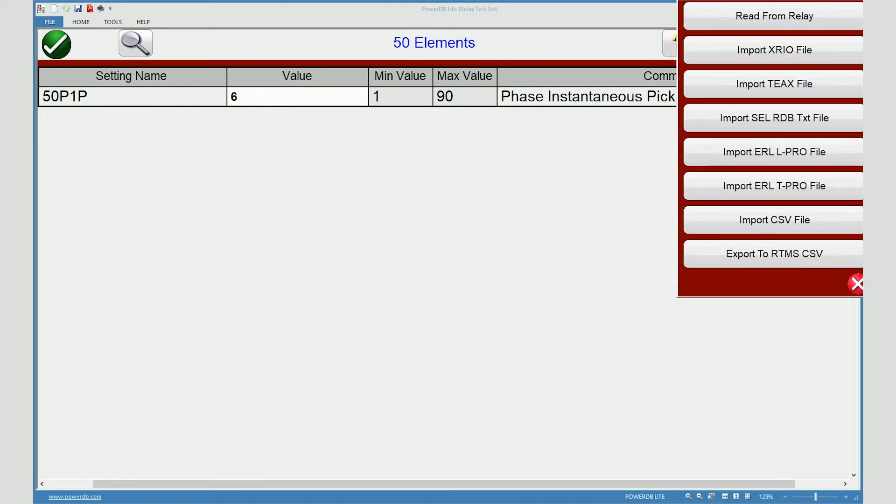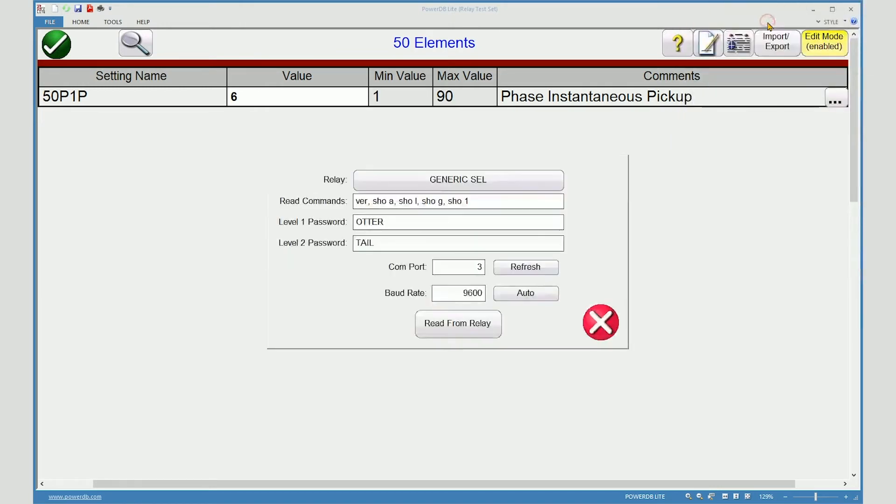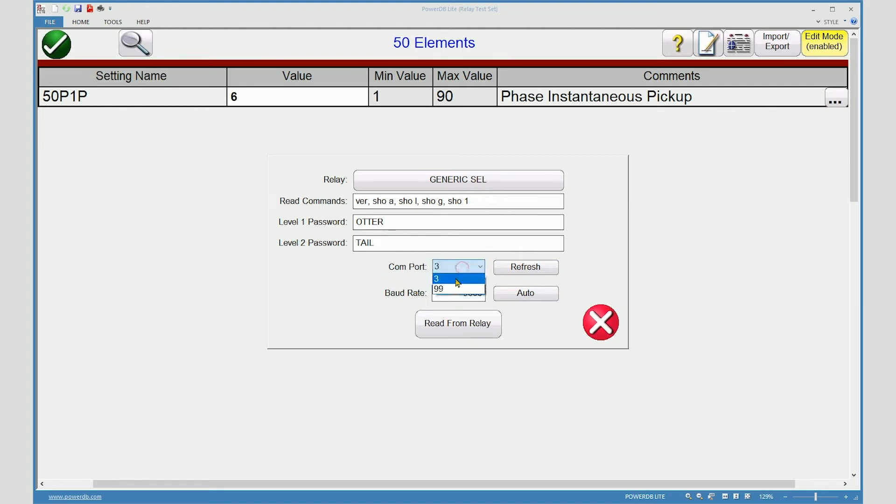Now I will demonstrate downloading settings from an SEL relay. These are the default commands that will be issued to the relay. You must know the password for level 1 and level 2. You must know your COM port and the baud rate.